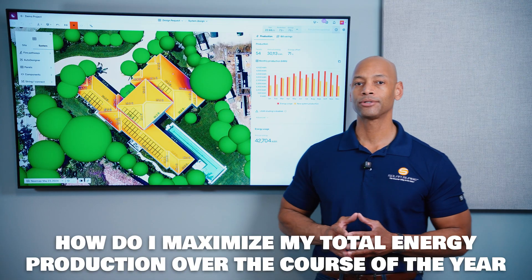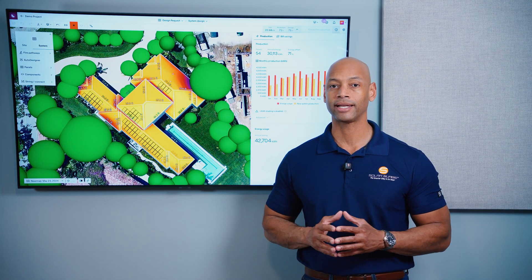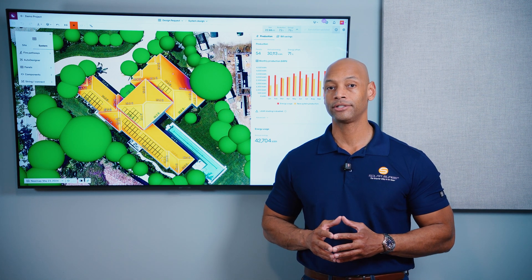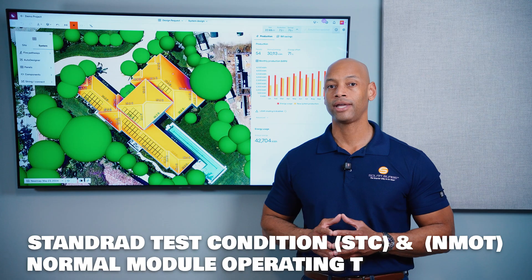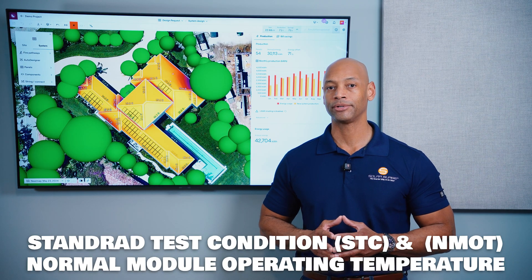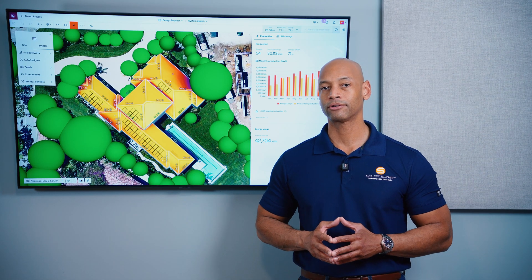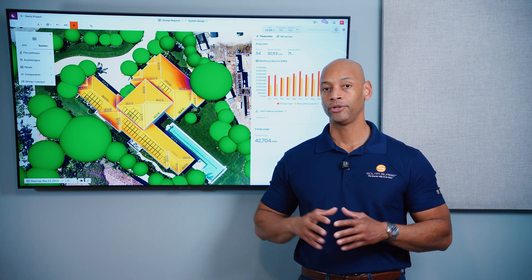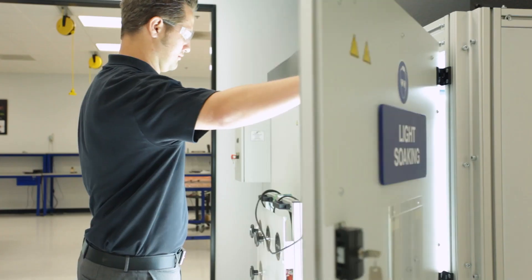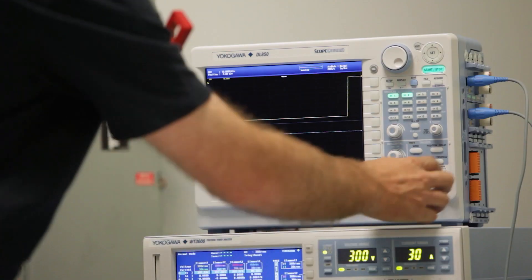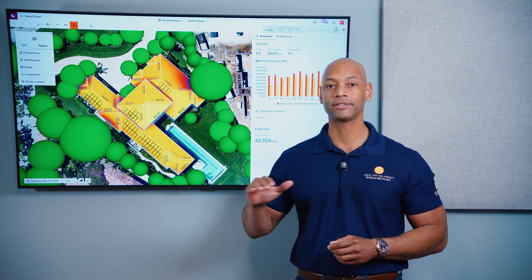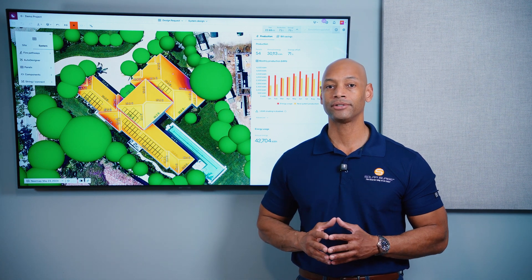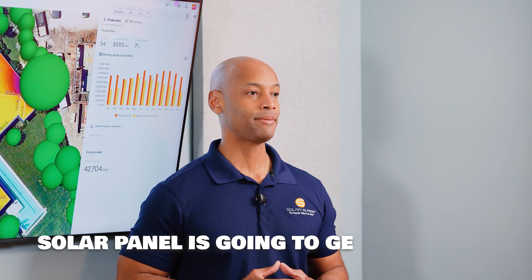I like to take a step back and explain how solar panels are tested and how they get their power rating, because solar panels are rated under two different sets of conditions. You have standard test conditions — or STC — as well as NMOT, or normal module operating temperature, which you can think of as more realistic real-world conditions. Under standard test conditions, tested in a laboratory, sunlight is applied directly to the solar panel surface at 1,000 watts per square meter and the temperature is kept at 25 degrees Celsius or 77 degrees Fahrenheit — cool, perfect, ideal lab conditions. That's where the solar panel gets stamped with its nameplate power rating.